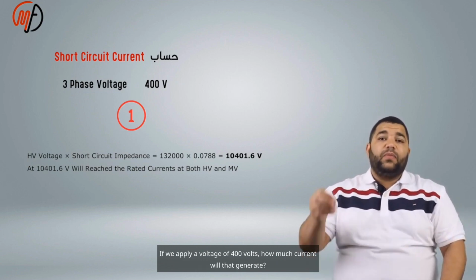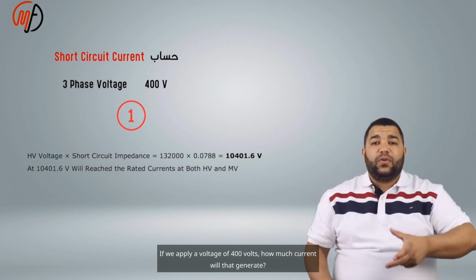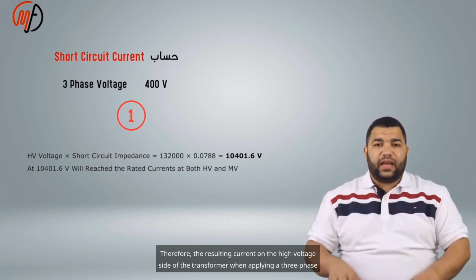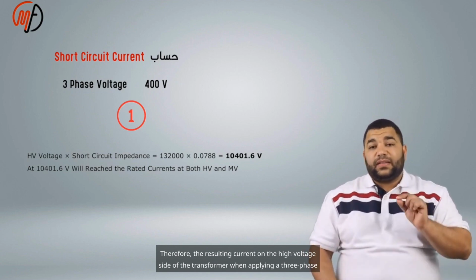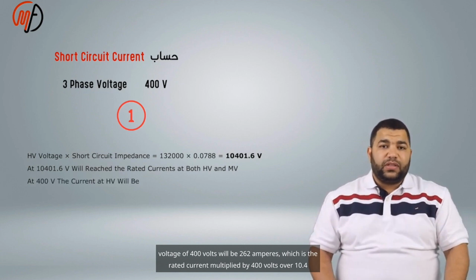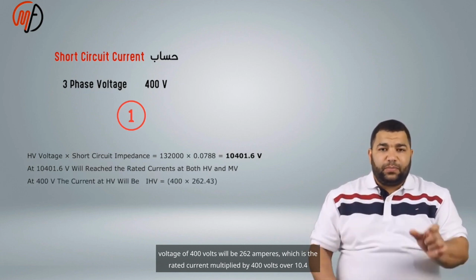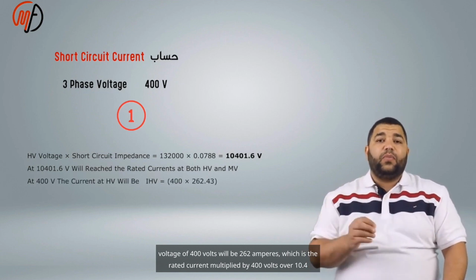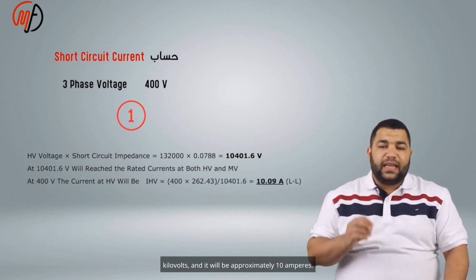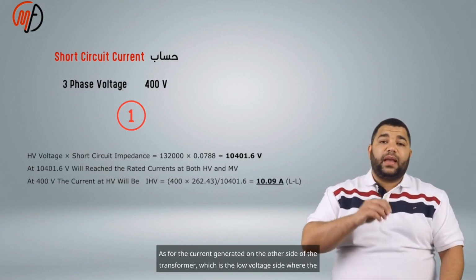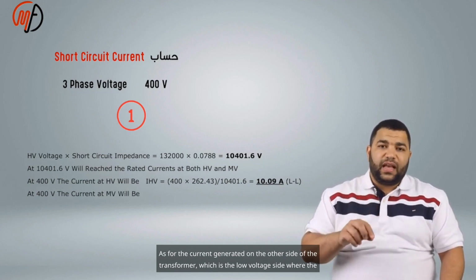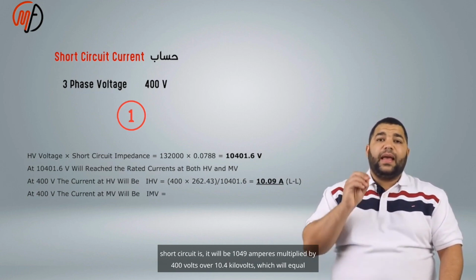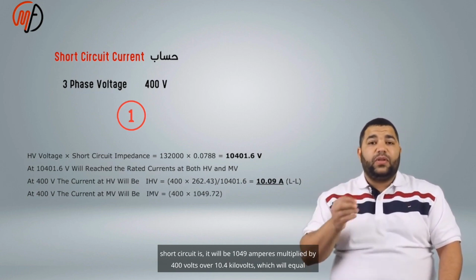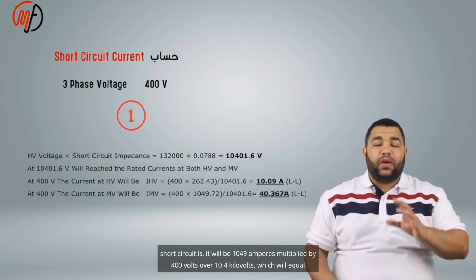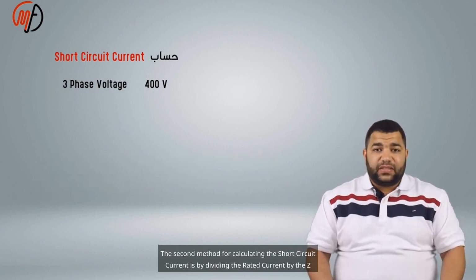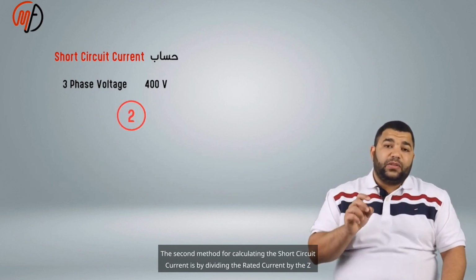If we apply a voltage of 400 volts, how much current will that generate? Therefore, the resulting current on the high voltage side of the transformer, when applying a three-phase voltage of 400 volts, will be 262 amperes, which is the rated current, multiplied by 400 volts over 10.4 kilovolts, and it will be approximately 10 amperes. As for the current generated on the low voltage side where the short circuit is, it will be 1049 amperes, multiplied by 400 volts over 10.4 kilovolts, which will equal approximately 40 amperes.